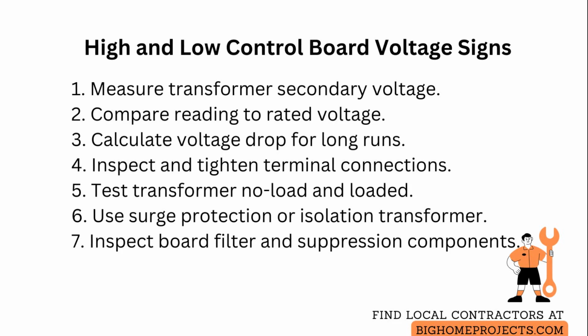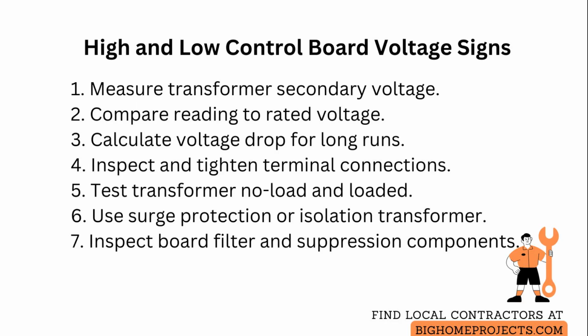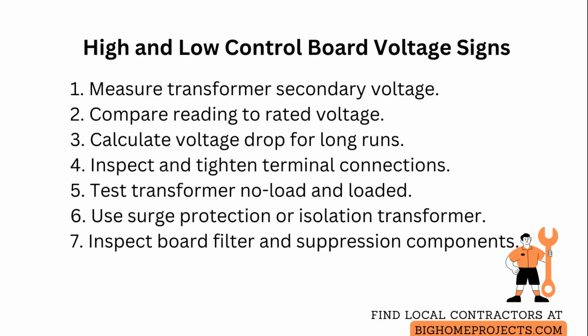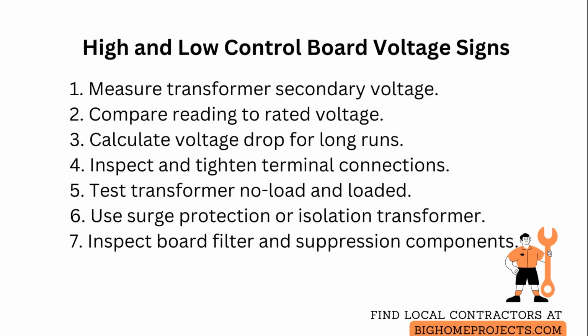A reading more than 10% above rated suggests a possible transformer overvoltage or a failing load regulator, while a reading more than 10% below rated points toward voltage drop from excessive conductor length, thin gauge wiring, high connection resistance, or a partially shorted circuit. Inspect wiring runs for length and gauge. Long runs with undersized conductors raise impedance and cause measurable low voltage under load.